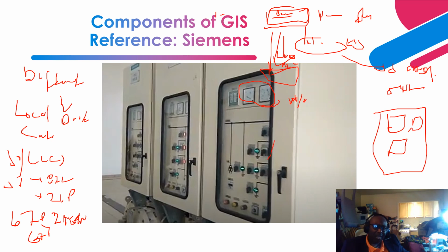Okay, so as you can see over here, this is a typical one line in each bay. So this has 3 bays, right? Okay, so in front of the local control cabinet is basically your one line. It goes through all the disconnect switches, all the earthing switches, all the circuit breakers. Basically, it gives you a pictorial view of what's inside the bay of the GIS. And this one is equivalent to the approved for construction single line drawing that you have after construction.